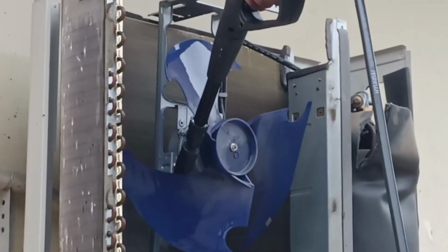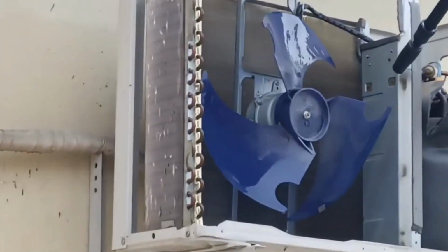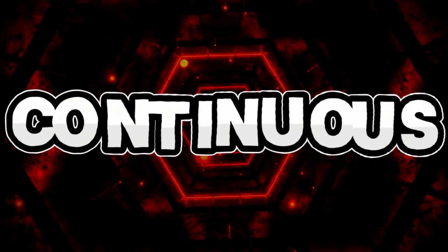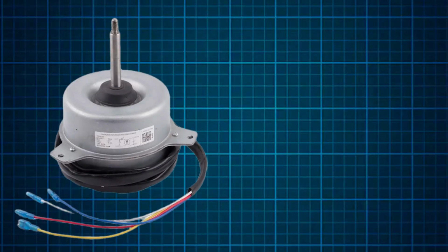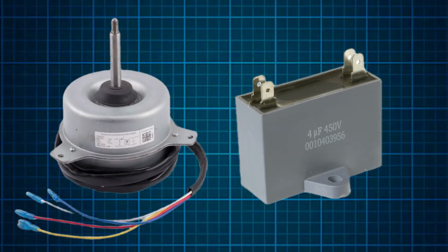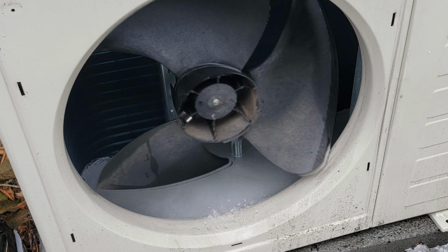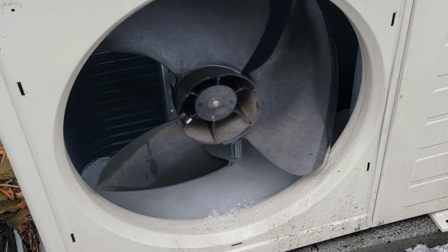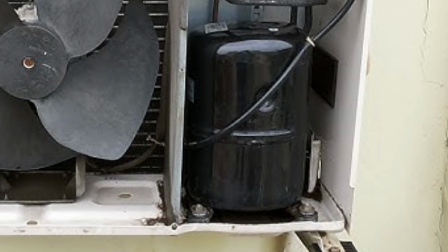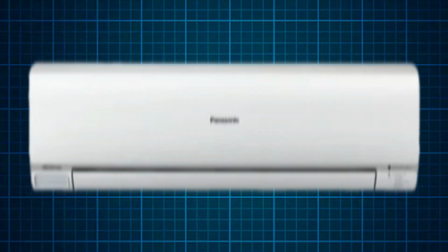If the condenser is very dirty, it can also cause problems. A dirty condenser reduces cooling efficiency, which may cause the unit to trip. In this case, you should clean the condenser thoroughly and check if the problem persists. If the problem continues, inspect the fan motor to see if it's running slowly or if its capacitor is weak. A slow fan can lead to overheating and tripping issues. Once you've checked all these things, if the compressor is still tripping suddenly, it could be an indoor unit issue.